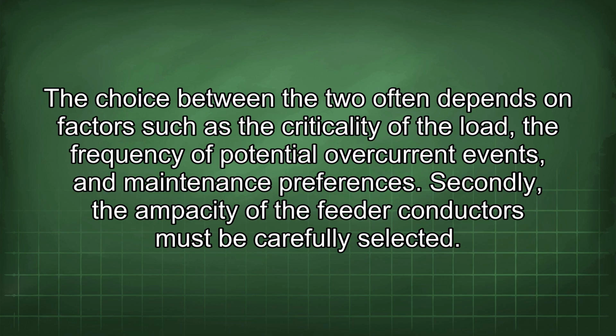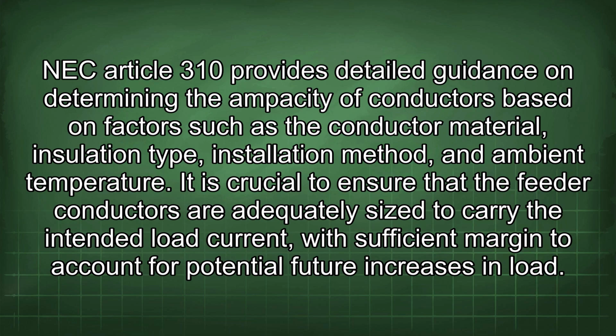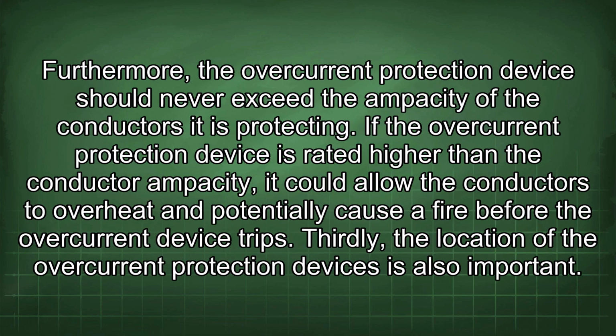Secondly, the ampacity of the feeder conductors must be carefully selected. NEC Article 310 provides detailed guidance on determining the ampacity of conductors based on factors such as the conductor material, insulation type, installation method, and ambient temperature. It is crucial to ensure that the feeder conductors are adequately sized to carry the intended load current, with sufficient margin to account for potential future increases in load. Furthermore, the overcurrent protection device should never exceed the ampacity of the conductors it is protecting. If the overcurrent protection device is rated higher than the conductor ampacity, it could allow the conductors to overheat and potentially cause a fire before the overcurrent device trips.